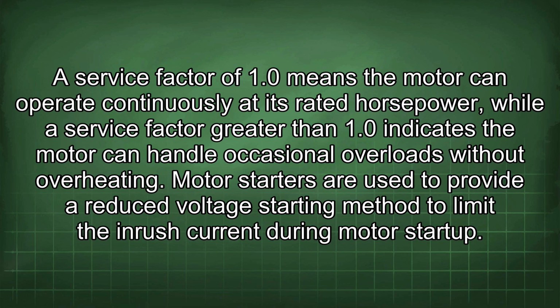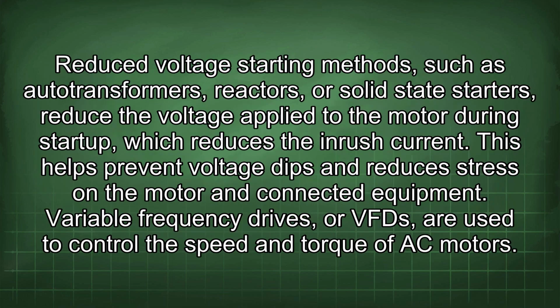Motor starters are used to provide a reduced voltage starting method to limit the inrush current during motor startup. Reduced voltage starting methods such as autotransformers, reactors, or solid-state starters reduce the voltage applied to the motor during startup, which reduces the inrush current. This helps prevent voltage dips and reduces stress in the motor and connected equipment.